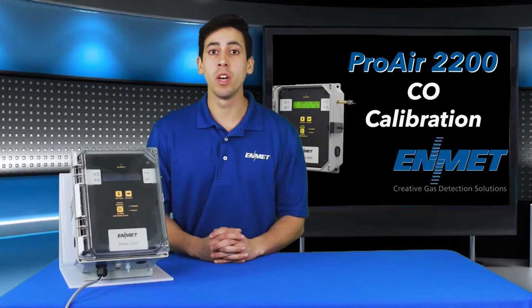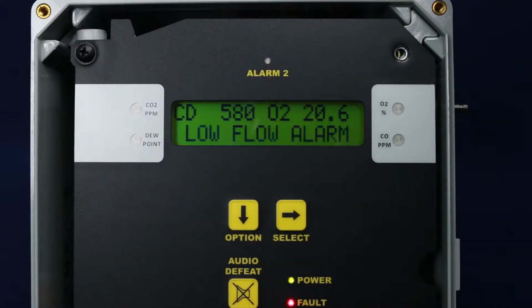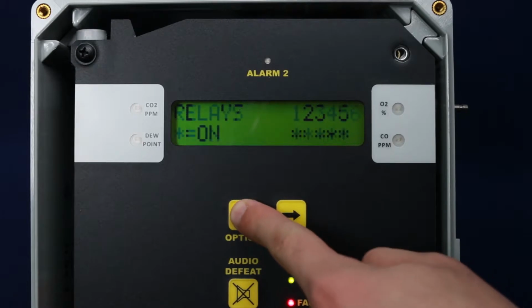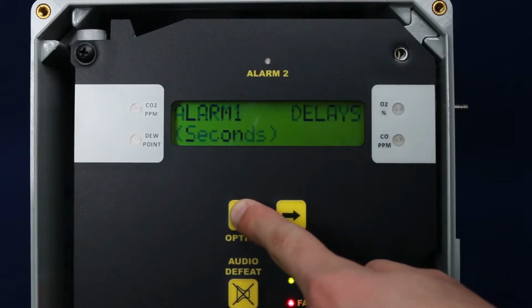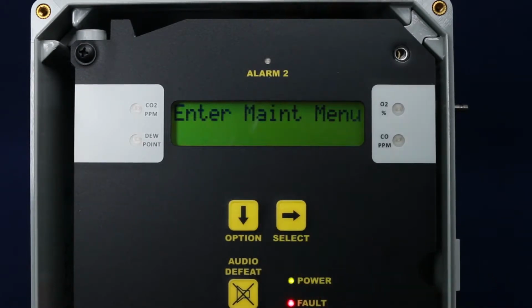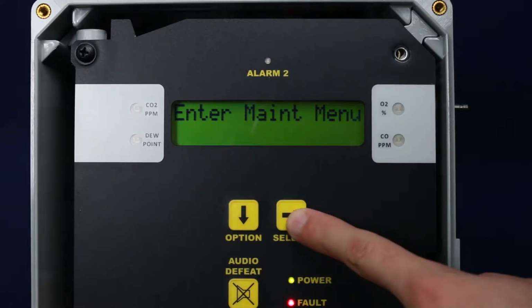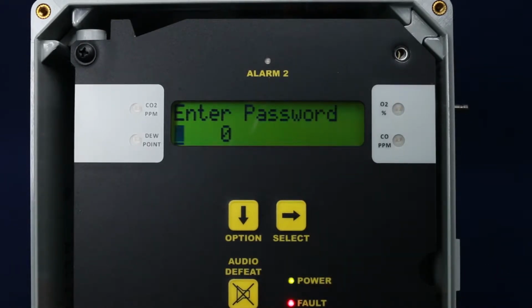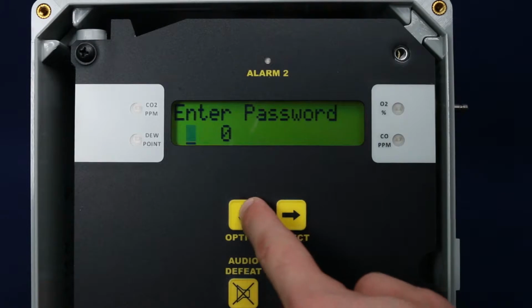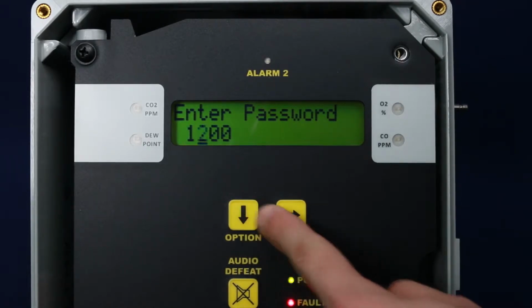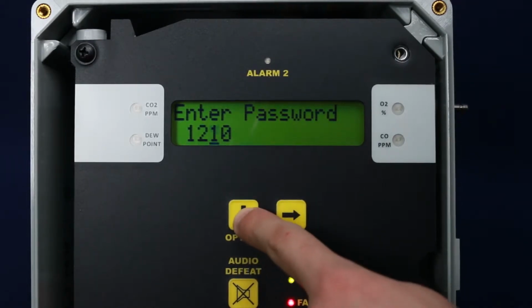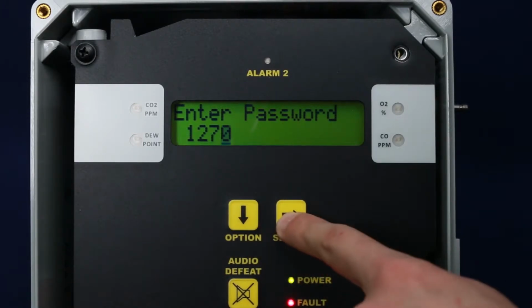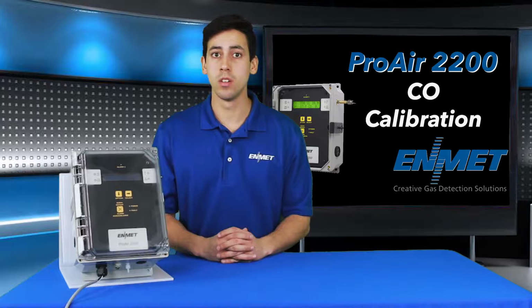To begin the calibration procedure, you will first need to enter the maintenance menu. To enter the maintenance menu, press the option button until Enter Maintenance Menu is displayed. Then you'll press Select to enter it. The password you need to enter is 1210, which is the default password. If that one does not work, then you may want to try 3663, which is the alternative password.